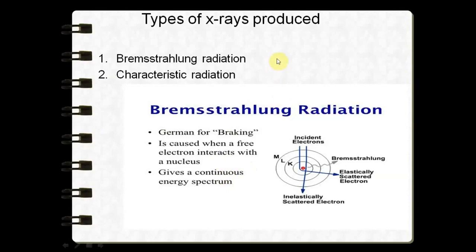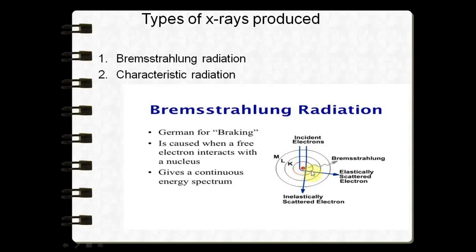Two types of x-rays are produced: bremsstrahlung radiation and characteristic radiation. Bremsstrahlung radiation comprises around 70% of the x-rays produced. 'Bremsstrahlung' is a German term meaning 'braking,' referring to the sudden braking of high-speed electrons when they hit the tungsten target in the anode. The incident electron is attracted towards the positively charged nucleus, slows down near the nucleus, and releases an x-ray photon.